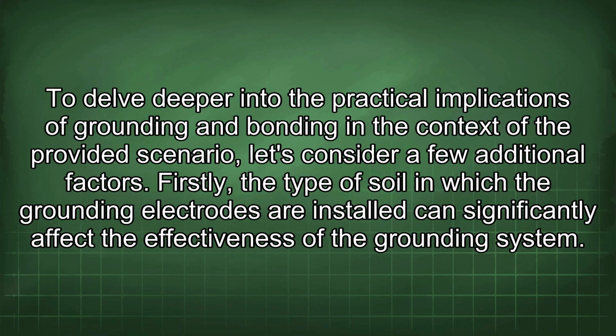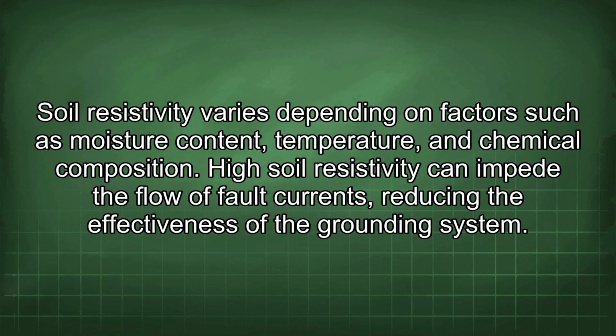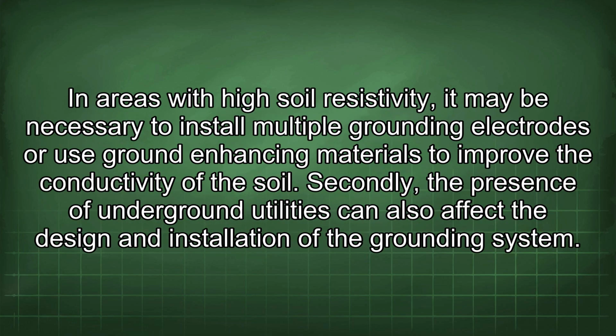To delve deeper into the practical implications of grounding and bonding in the context of the provided scenario, let's consider a few additional factors. Firstly, the type of soil in which the grounding electrodes are installed can significantly affect the effectiveness of the grounding system. Soil resistivity varies depending on factors such as moisture content, temperature, and chemical composition. High soil resistivity can impede the flow of fault currents, reducing the effectiveness of the grounding system. In areas with high soil resistivity, it may be necessary to install multiple grounding electrodes or use ground-enhancing materials to improve the conductivity of the soil.